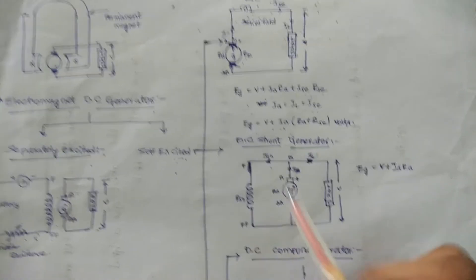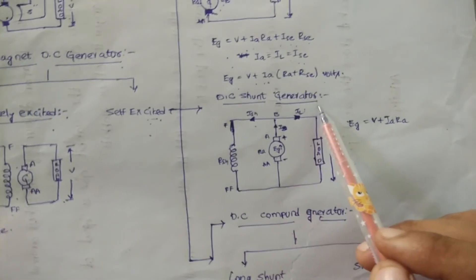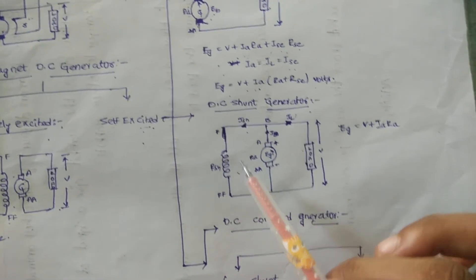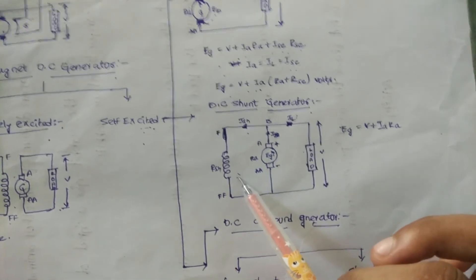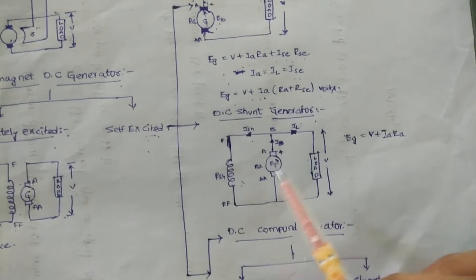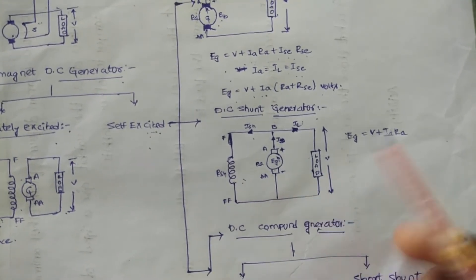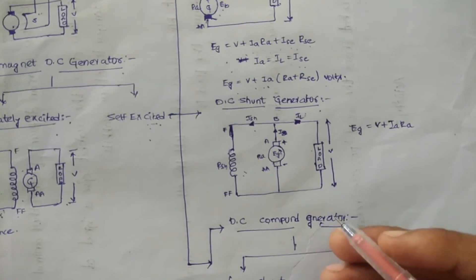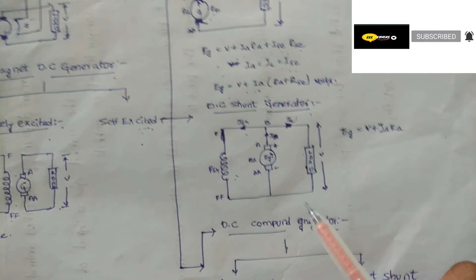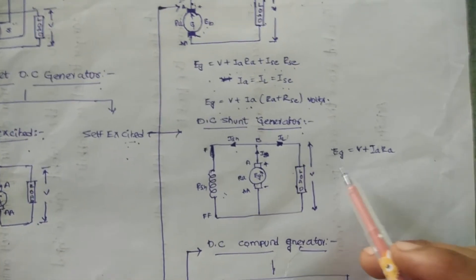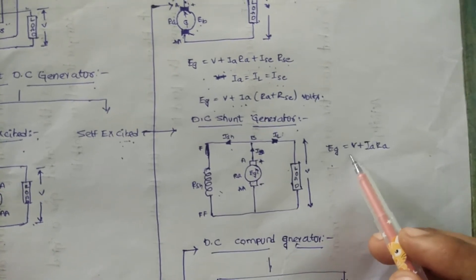In the DC shunt generator, the field winding is connected in parallel across the armature, as shown in the figure. The current flowing through the shunt field winding is about 5% of the rated armature current. Hence the shunt field winding is designed with many turns of wire, giving a high resistance of the order of 100 ohms. The voltage across the shunt field is the same as the terminal voltage. The EMF equation is: Eg = V + Ia·Ra.